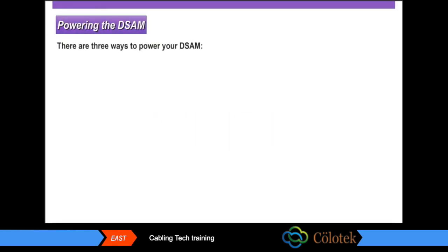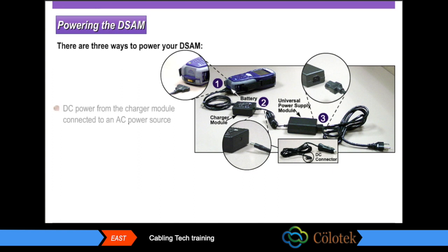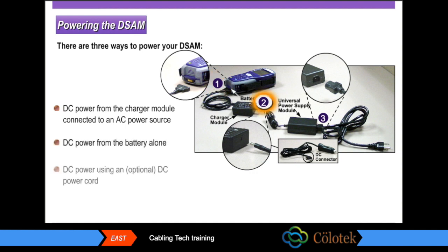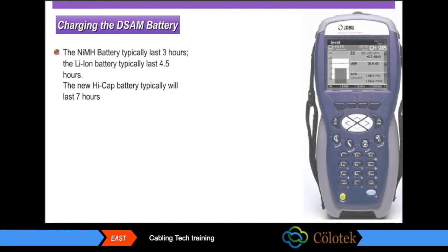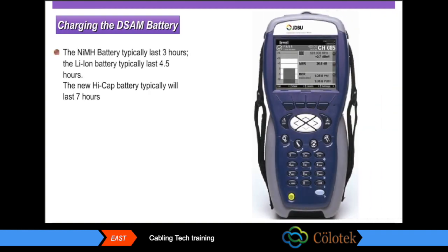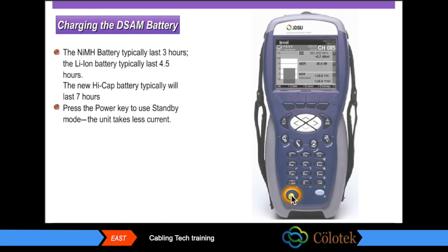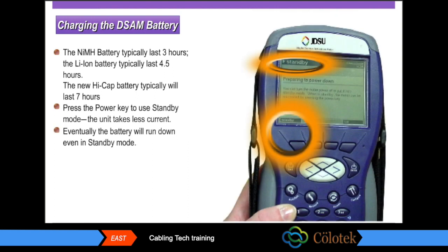There are three ways to provide power to your DSAM: DC power from the charger module connected to an AC power source, DC power from the battery alone, or DC power using an optional DC power cord. The nickel metal hydride battery lasts three hours, the lithium ion battery typically lasts 4.5 hours, and the new high cap battery typically will last seven hours. Press the power key to use the standby mode; the unit will take less current.